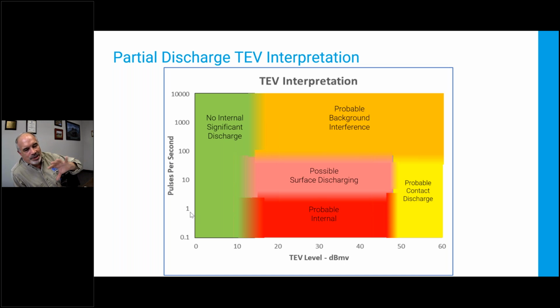If you look at a sine wave and say, well, I discharge at my peak voltage on the top and I discharge at my peak voltage at the bottom, then I'm talking about 2 pulses per cycle. Maybe it's bad enough that I can charge, discharge, and charge and discharge again in a half cycle. I get 4 pulses per cycle. That's pretty reasonable for internal. And that's where you see this red box. Internal, our levels, you know, anything below 10, 15 dB, 20 dB even, I'm not that excited about. I get 30, 40, 50 with 2 pulses per cycle, I'm really looking at internal discharge.